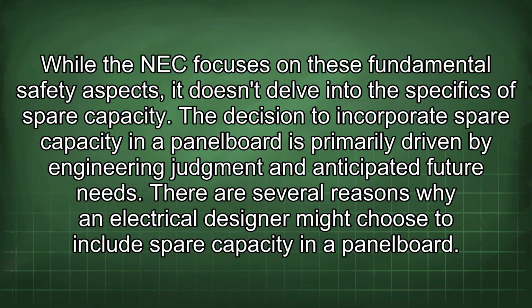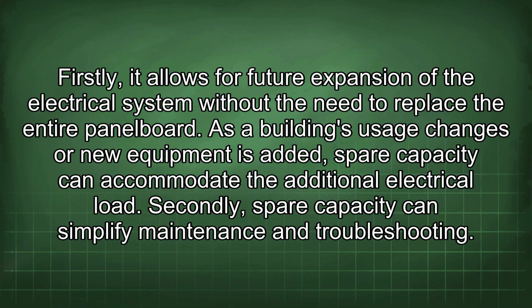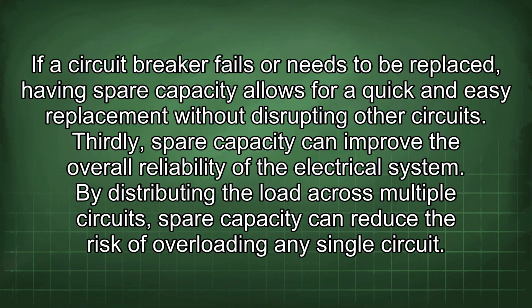There are several reasons why an electrical designer might choose to include spare capacity in a panel board. Firstly, it allows for future expansion of the electrical system without the need to replace the entire panel board. As a building's usage changes or new equipment is added, spare capacity can accommodate the additional electrical load. Secondly, spare capacity can simplify maintenance and troubleshooting. If a circuit breaker fails or needs to be replaced, having spare capacity allows for a quick and easy replacement without disrupting other circuits. Thirdly, spare capacity can improve the overall reliability of the electrical system. By distributing the load across multiple circuits, spare capacity can reduce the risk of overloading any single circuit.